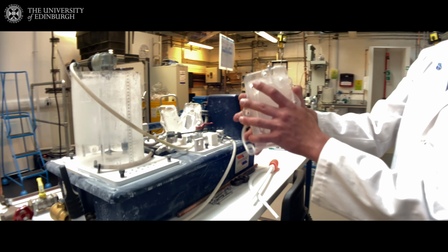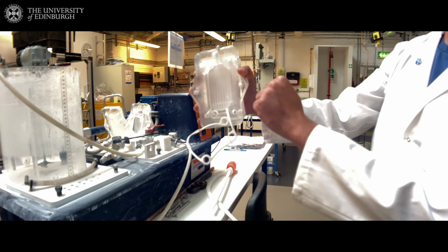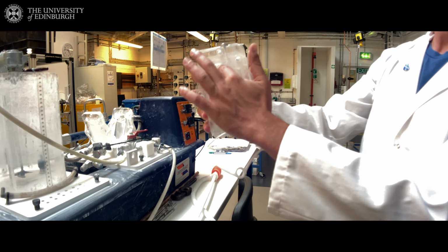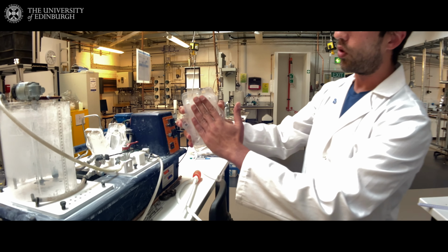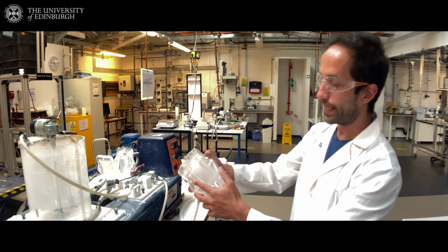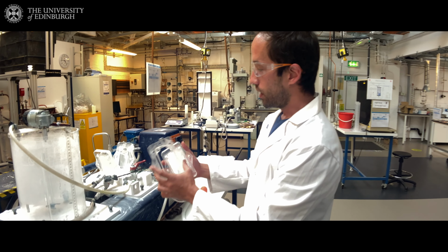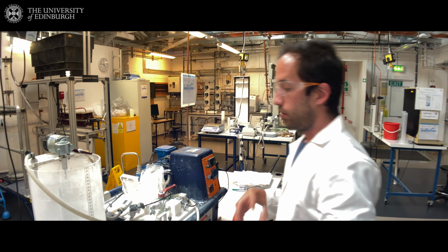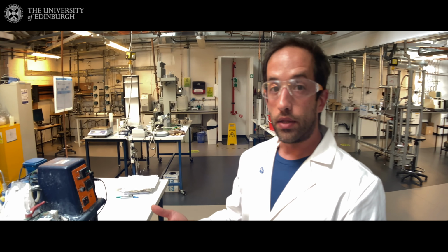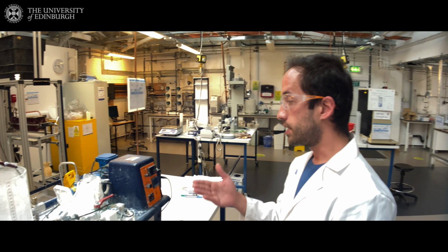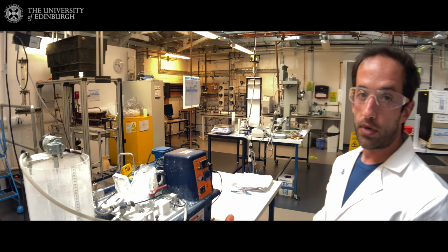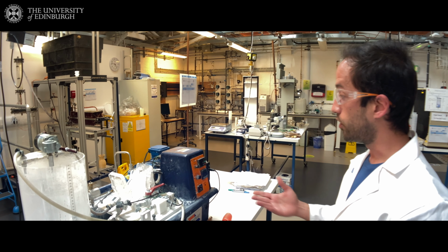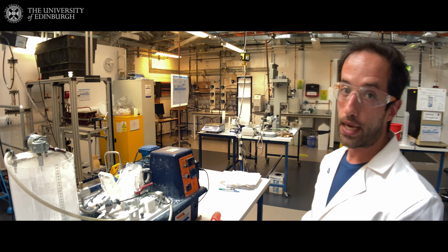Because the flow will be from left to right, we will start to obtain the filtrate, creating a cake. What this experiment consists of is passing different flows and different working pressures, and seeing the hydrodynamic performance of the equipment.